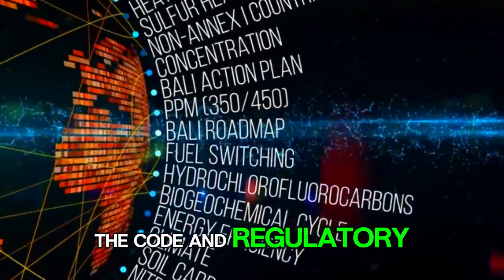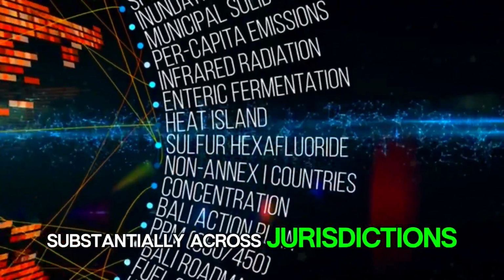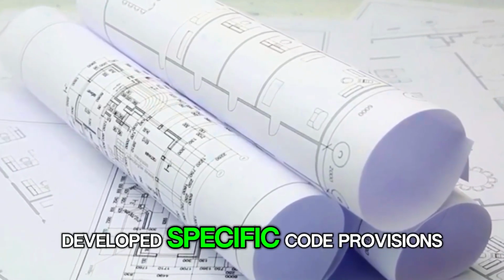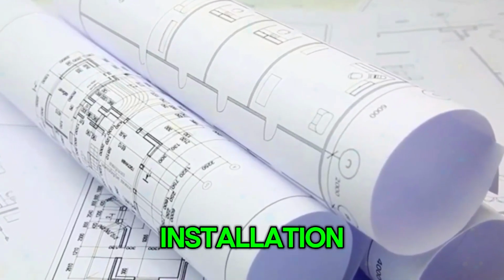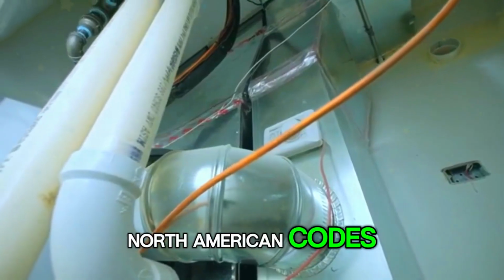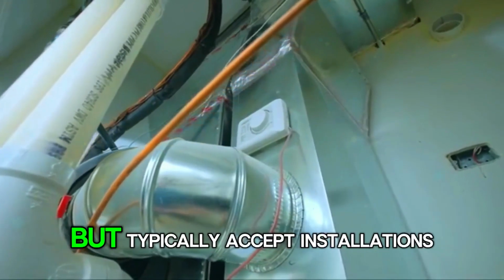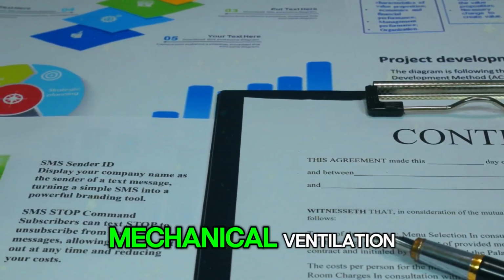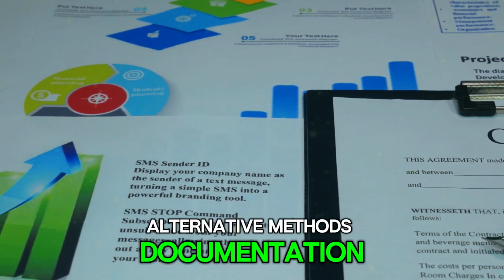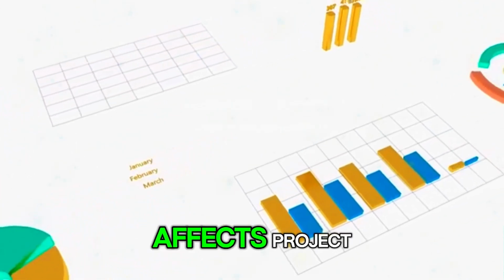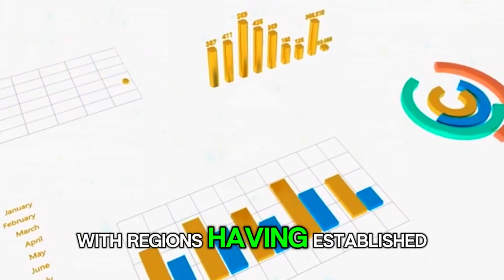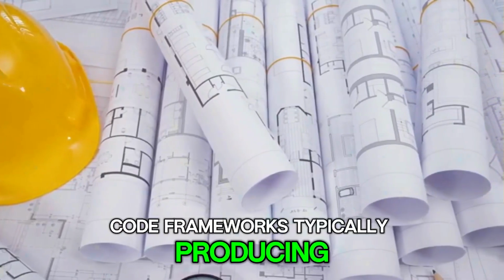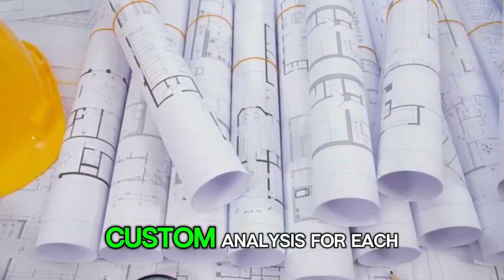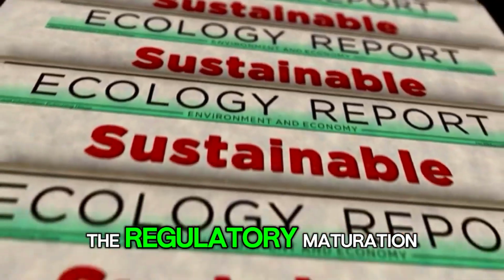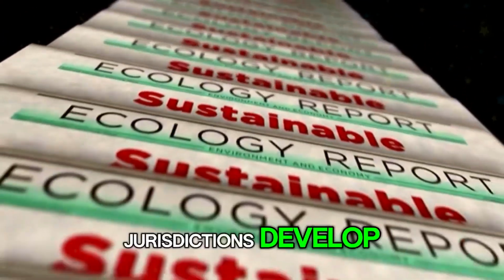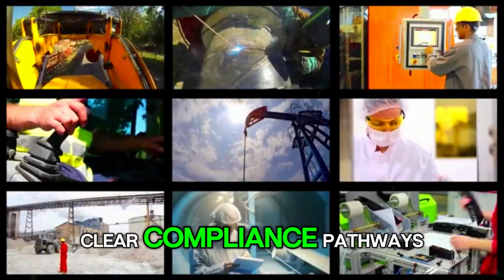The code and regulatory treatment of earth tubes varies substantially across jurisdictions. Some European countries have developed specific code provisions addressing earth tube design, installation, and operational requirements. North American codes generally lack specific earth tube provisions, but typically accept installations that meet general mechanical ventilation requirements through alternative methods documentation. The regulatory treatment affects project feasibility and costs, with regions having established code frameworks typically producing smoother project execution than regions requiring custom analysis for each installation. The regulatory maturation continues as more jurisdictions develop experience with the technology and establish clear compliance pathways.